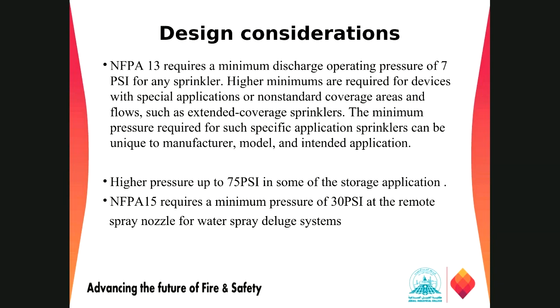NFPA 15, which is for deluge water spray systems, says they need a minimum of 30 psi for the spray nozzles. Here we have one table which says what is the minimum residual pressure required for different fire protection equipment. 100 psi is the maximum one. For the monitors, 100 psi. For the hose reel, 100 psi. For the hydrant, we need 100 psi. For the deluge nozzles, 25 psi. And for the spray nozzles, 30 psi, and so on for all those kinds of applications.